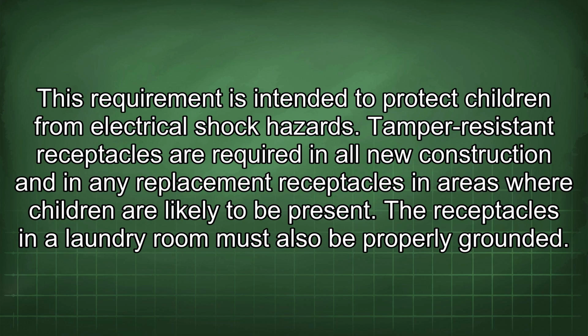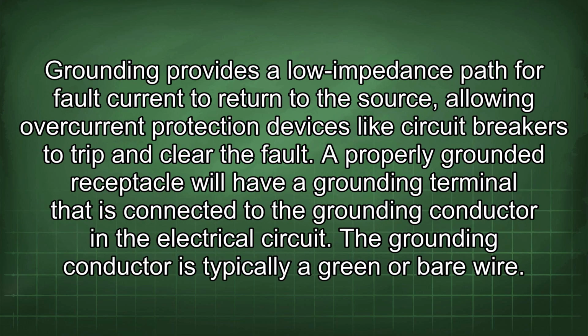Tamper-resistant receptacles are required in all new construction and in any replacement receptacles in areas where children are likely to be present. The receptacles in a laundry room must also be properly grounded. Grounding provides a low impedance path for fault current to return to the source, allowing overcurrent protection devices like circuit breakers to trip and clear the fault. A properly grounded receptacle will have a grounding terminal that is connected to the grounding conductor in the electrical circuit. The grounding conductor is typically a green or bare wire.